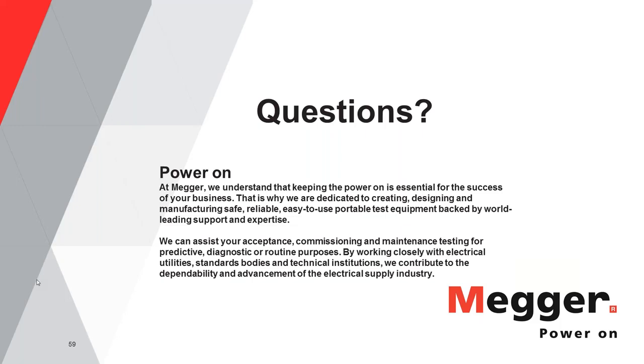All right. Next question is, what equipment is recommended to make the primary injection? I'm not quite sure if I understood your question, but as I said earlier, you need a high current source to run a primary injection test, and the type of test set, the size of the test set that you get, will depend on the size of the breakers that you will need to test.